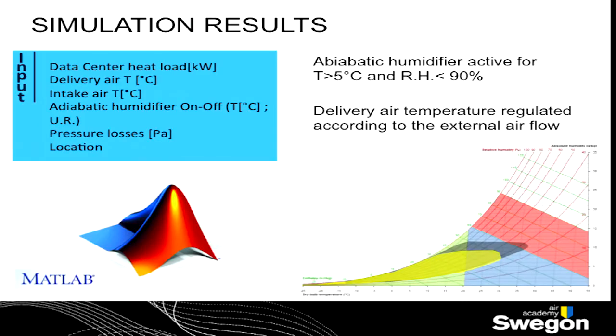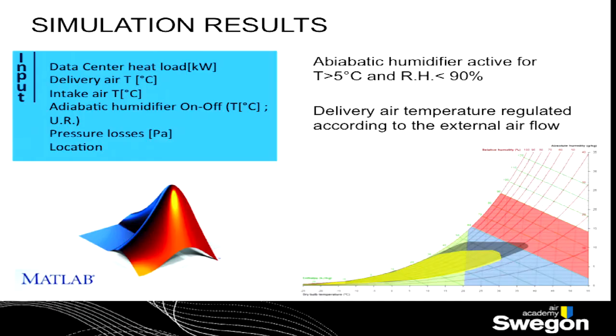We performed our analysis with MATLAB, considering an adiabatic humidifier which is active for temperatures higher than 5 degrees. Why? Not because 5 degrees are not enough to have a total free cooling, but because the energy spent adding the adiabatic cooling is less than what we earn decreasing the speed of the fan. Okay, so we have a benefit in switching on the evaporative cooling system at the lowest temperature possible. Of course, not lower than 5 degrees because of a problem with the ice. Okay, so these are the conditions for the calculation that we are going on with now.